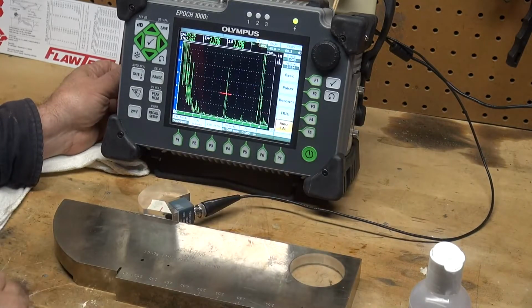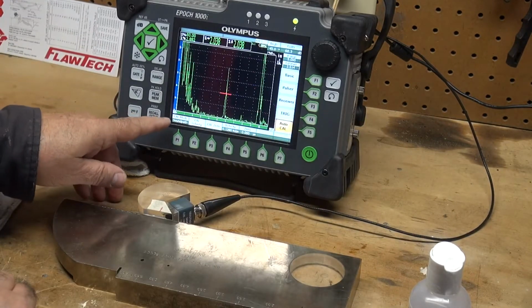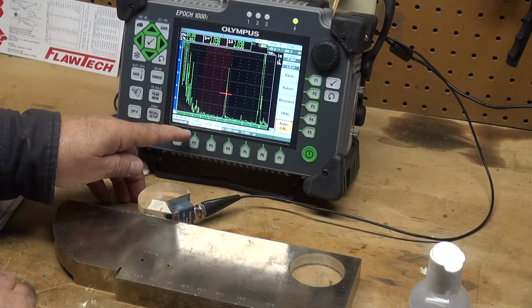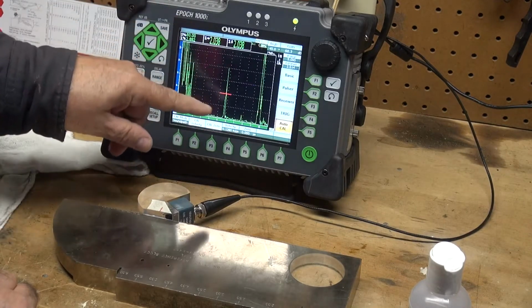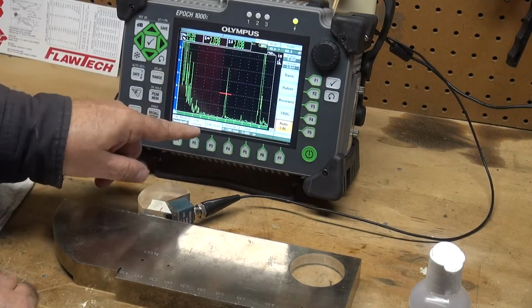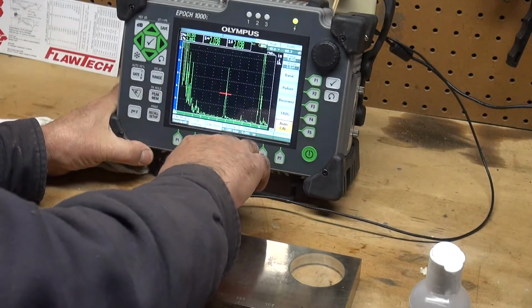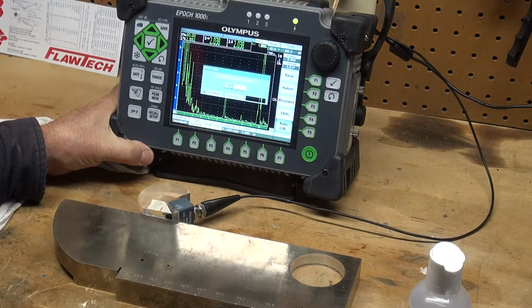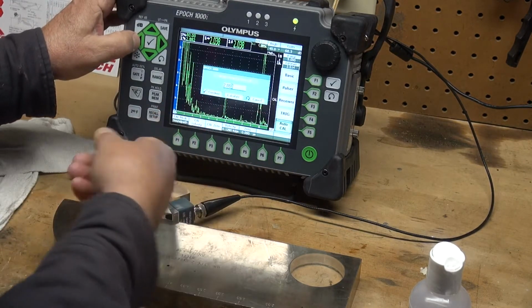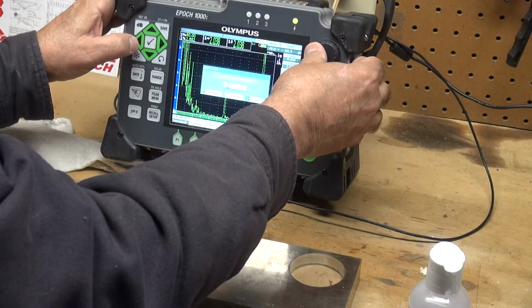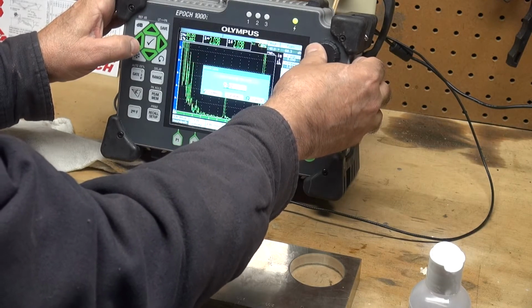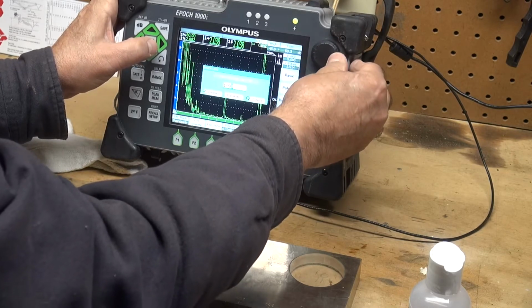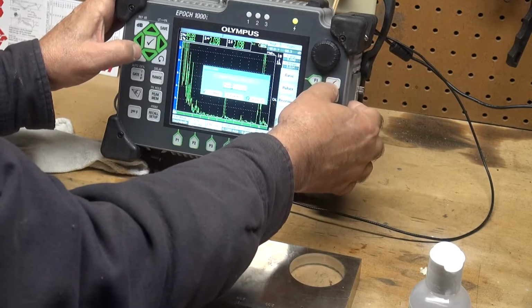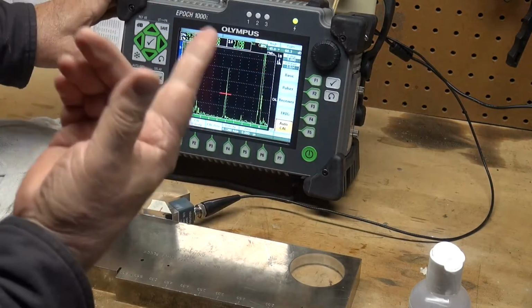I want to push my AutoCal button, and AutoCal comes up, calibration mode, sound path. There's a cal velocity and a cal 0. That 2 inch radius that's reflecting back, I want to press cal 0 to calibrate the 0 of my machine, and the machine comes back and wants to know what that value is. So I'm going to change that value to say that that sound path is 2 inches. Press the check to continue. So I stored that value.